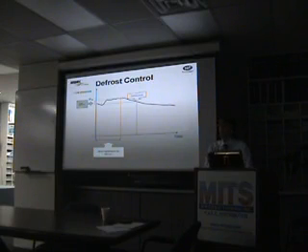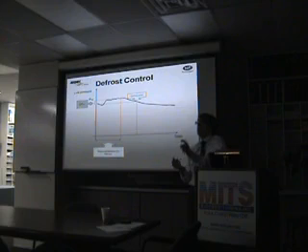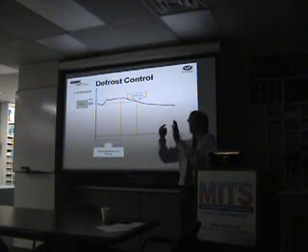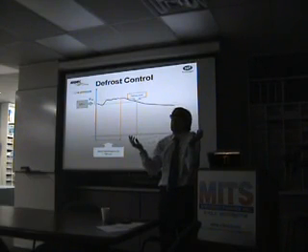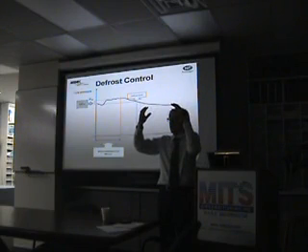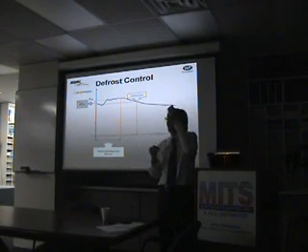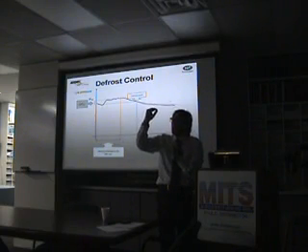Because if it depends only on the pressure, then you might have a problem too, like the leaves on the coil or whatever. Exactly. Could be other reason. But if you have, let me say, a dirty coil, you fix the pressure, but the way we check, being dynamic, we don't measure a value of pressure. Actually, if we have a dirty coil, we have a higher pressure, we increase the pressure, but we don't check the real value of the coil. We check just how much we drop if the temperature condition is what we measure.